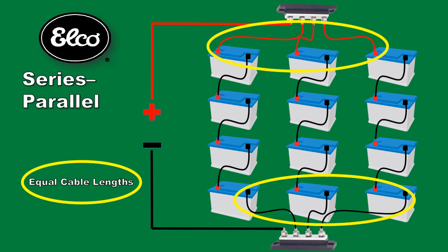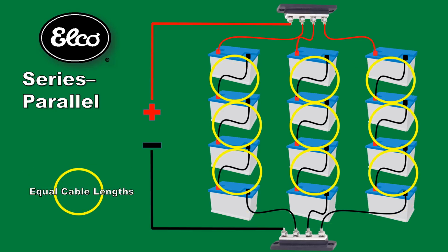Try to place the bus bars so that the cable lengths are optimized to shorter lengths. Also, all interconnecting cable lengths within battery strings must be equal length. This is particularly important for AGM installations to maximize battery longevity and prevent damaging batteries.